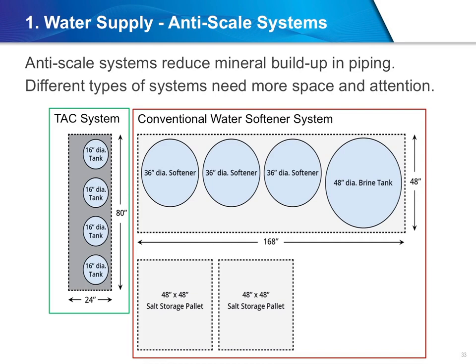The solution here is an anti-scale system. A conventional system typically relies on the use of salts that need to be constantly replenished into the system as water flows through it. Salt also has a very large footprint. An alternative is to use a template-assisted crystalline, or TAC, system which eliminates the need for salt, takes up less square footage, and is generally regarded as much more economical with similar results. While reduction of scale and sediment doesn't directly kill Legionella, it makes all other Legionella-reducing solutions work more effectively.